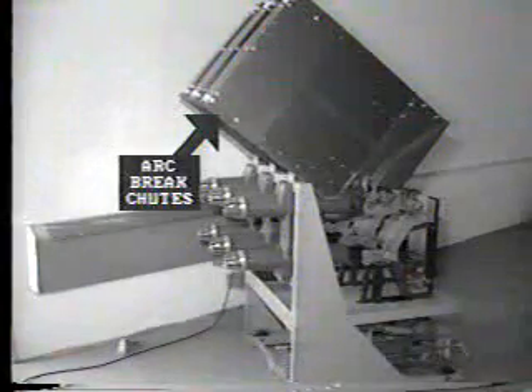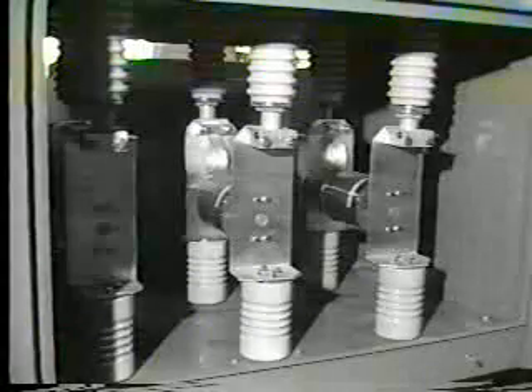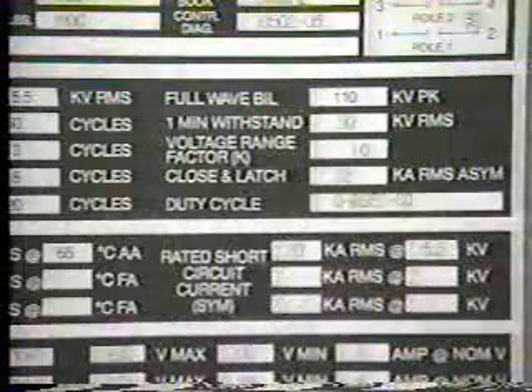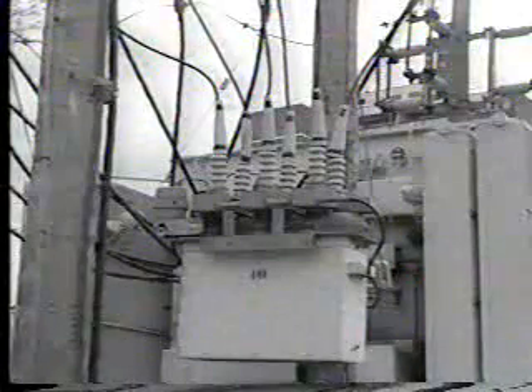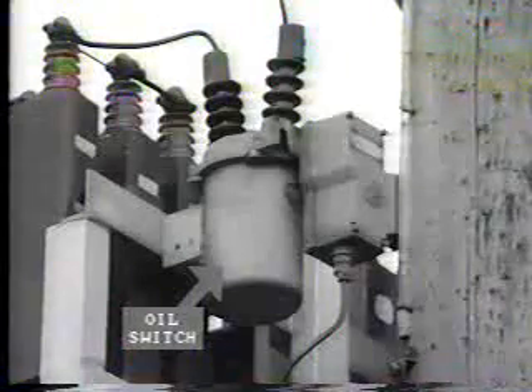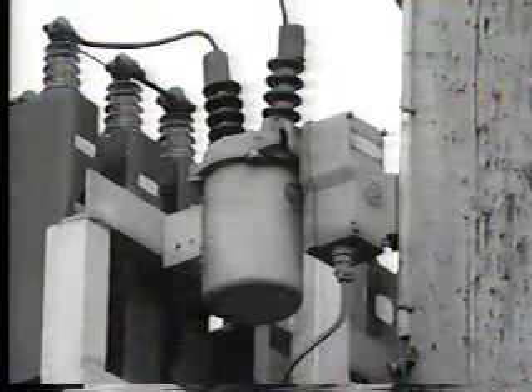Yet another quenching medium is SF6, sulfur hexafluoride gas. And in lower voltage breakers, arc break chutes are provided. Vacuum breakers use vacuum as the arc quenching medium. The subject of circuit breaker design is obviously outside the scope of this video program, but further details are provided in other programs. The important factor to remember is that the circuit breaker is capable of interrupting fault currents. There are many other switching devices, particularly in use on the distribution system, such as reclosers, sectionalizers, and oil switches. But in general, these are capable of very limited fault interruption.